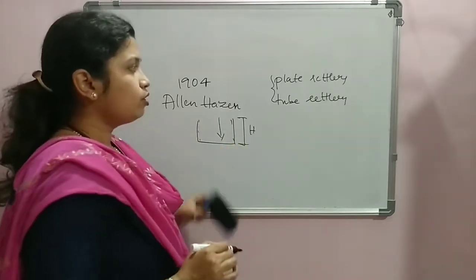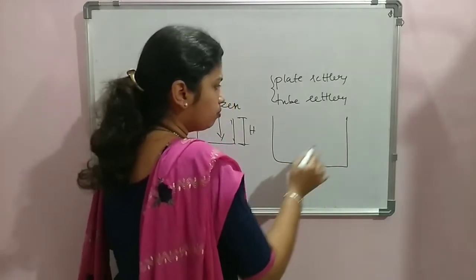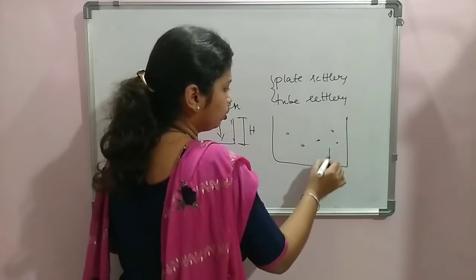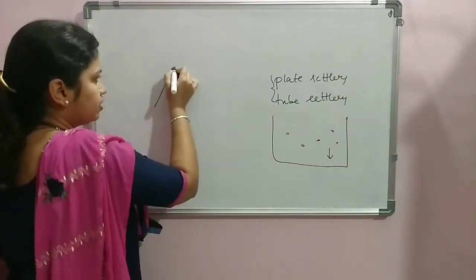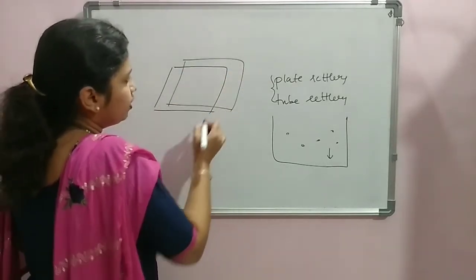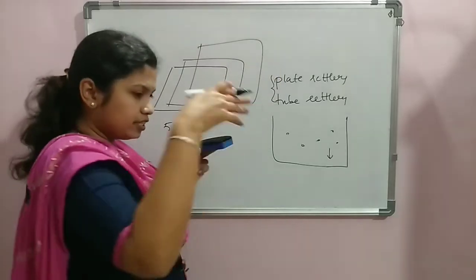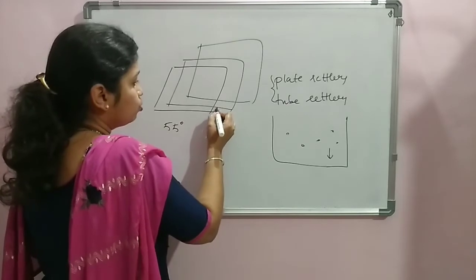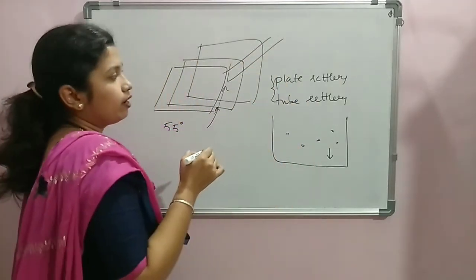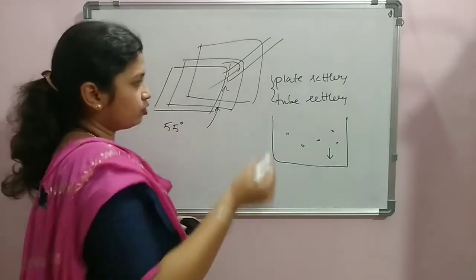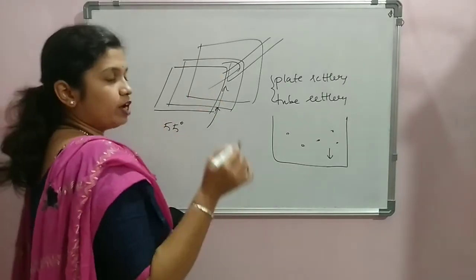By using plate settlers and tube settlers, we change the process. In an empty tank, particles settle slowly under gravity. By replacing the empty space with plates or tubes, we improve settling. For plate settlers, a series of slanted plates at around 55 degrees are placed inside the tank. Water rises through bottom orifices and is collected by common collection channels connected to the plates, then taken out for the next process.